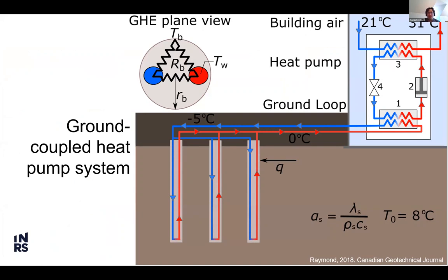So this slide shows you the operation of the heat pump system in typical, I would say, Canadian conditions. So our ground temperature is near 8 degrees Celsius in southern Canada. The idea is to send inside the pipe a mix of water and antifreeze. So the fluid temperature goes down to below 0 degrees Celsius, but doesn't freeze, right? Because there's freeze protection down to minus 15 degrees sometimes. It's at a colder temperature than the ground. So you extract heat from the ground, and then you recover fluid at 0 degrees Celsius.